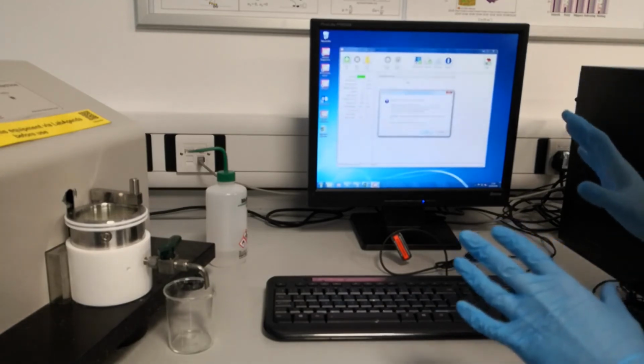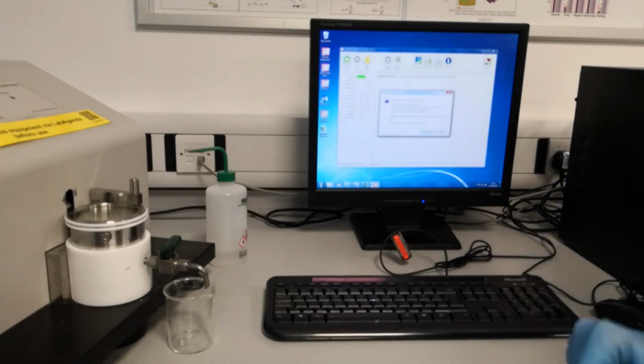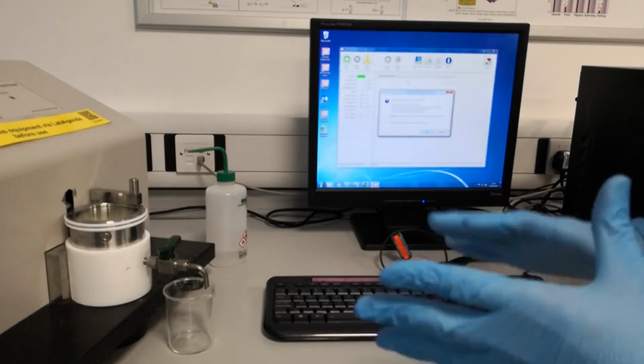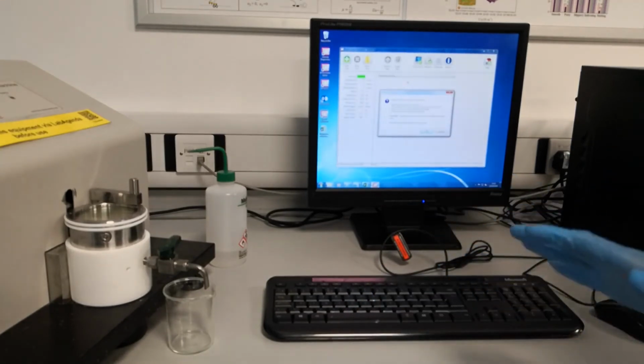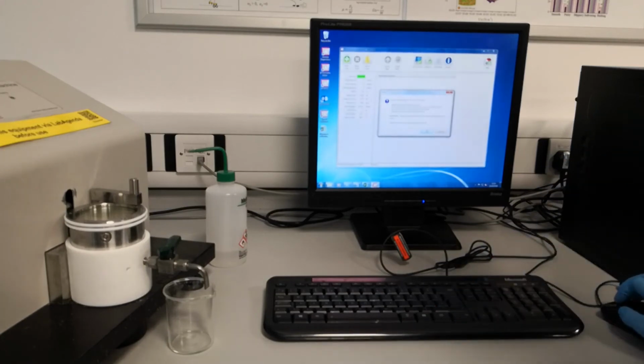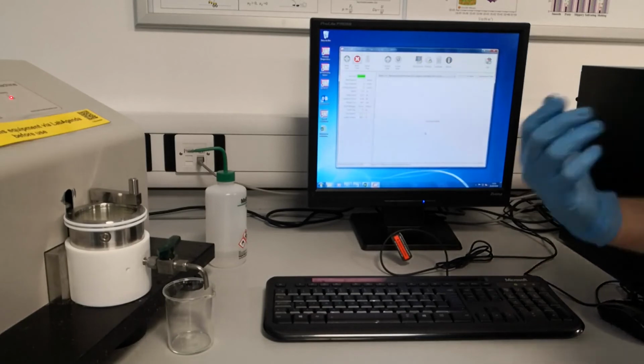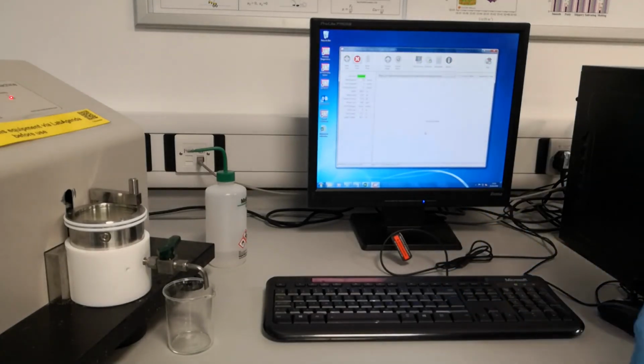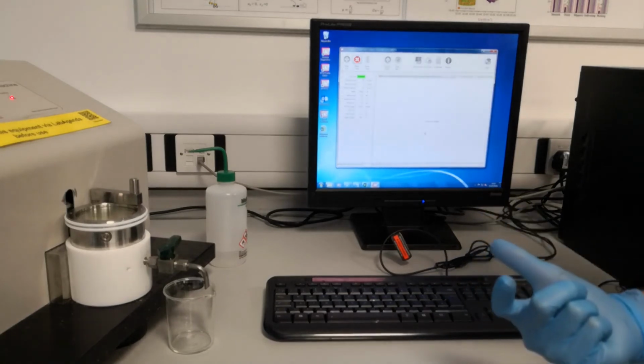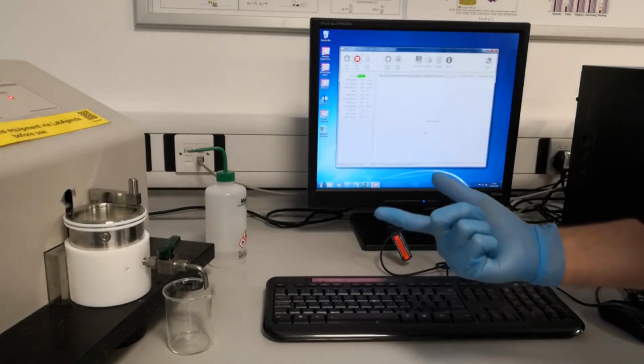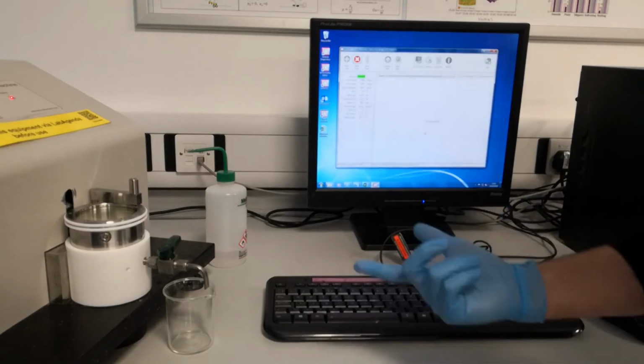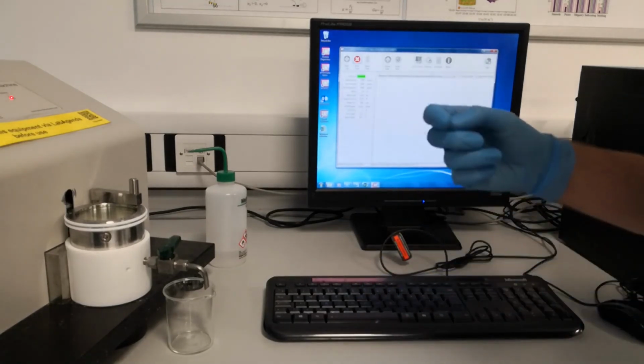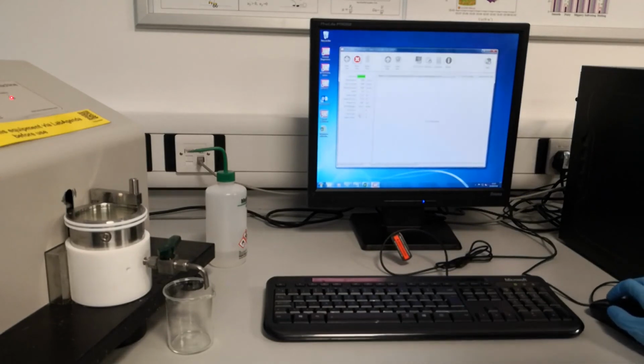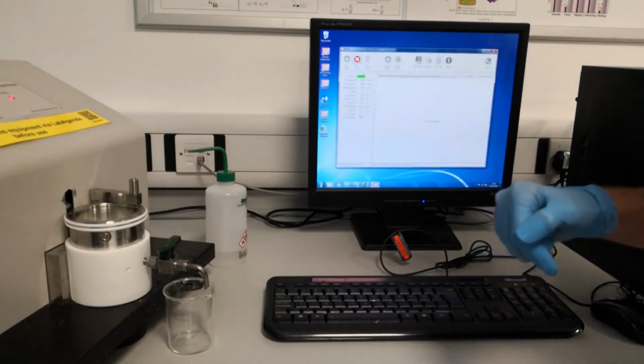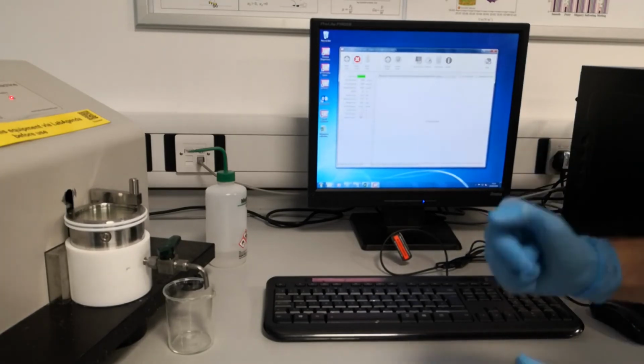In this case, a box would show up on the screen asking you to check whether the lid is secured and your samples are secured. When you are sure that all the samples are in place and you're happy to run the test, you press OK. The machine first heats up the lubricant to the desired temperature. Without applying a load, only with the disc and ball rotating, it heats up the lubricant to the desired temperature. As soon as it gets to 37, which is our desired lubricant temperature in this case, it would start the actual test.